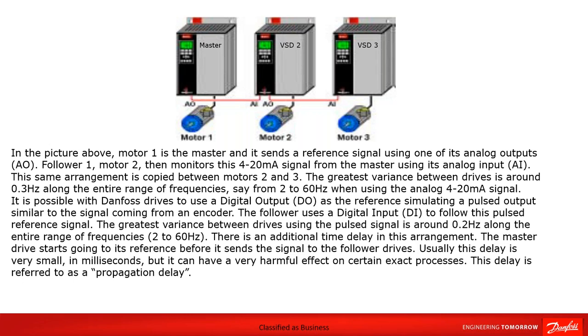It is possible with the Danfoss drives to use a digital output as the reference, simulating a pulsed output similar to the signal coming from an encoder. The follower uses a digital input then to follow this pulse reference signal. So the greatest variance between the drives using the pulse signal is around 0.2 hertz along the entire range of frequencies, again, 2 to 60 hertz. However, there's an additional time delay in this arrangement. The master drive starts going to its reference before it sends the signal to the follower drives. Usually this delay is very small, it's actually milliseconds. But it can have a very harmful effect if you've got certain exact processes that are required. And this delay is referred to as a propagation delay.